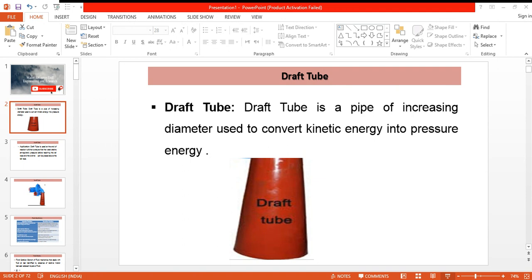The draft tube is used in reaction turbines where we want to ensure that the water attains atmospheric pressure before it comes out of the turbine at the tail race end, and this helps us in ensuring that the turbine is placed well above the tail race.